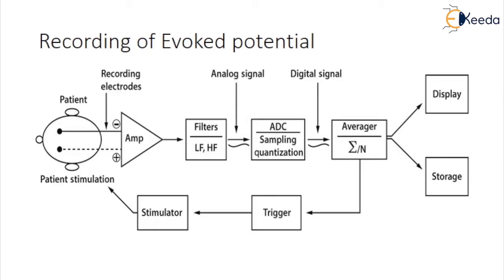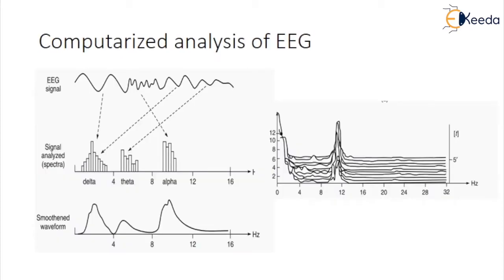The amplitude of evoked potentials are normally measured on a vertical scale with sample points measured as bits on a linear resolution scale. Resolution of voltage is usually sufficient with 8-bit recording, although 10 to 16-bit analog to digital systems are becoming available.